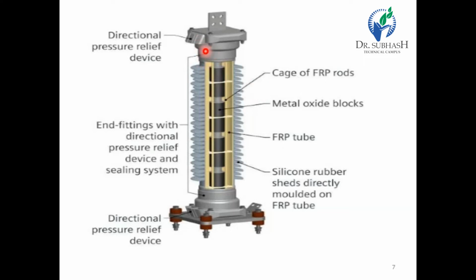This is the cross section view of a gapless metal oxide type arrestor. In this figure, in the middle there are black metal oxide blocks, and it is covered by an FRP tube. The yellow one is the FRP tube, and silicone rubber sheds are directly molded on the FRP tube. This one is the cage of FRP rods. At the upper and lower ends, there is a directional pressure relief device, one here and another one here. End fittings with directional pressure relief device and sealing system. So this one is the end fittings. So this is the whole about the arrestor.